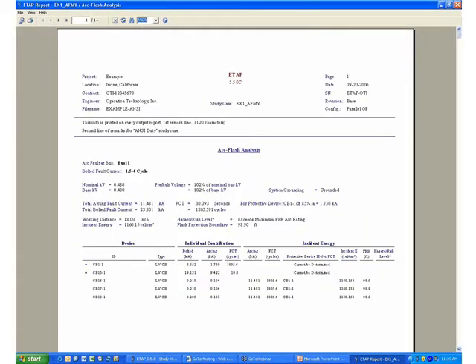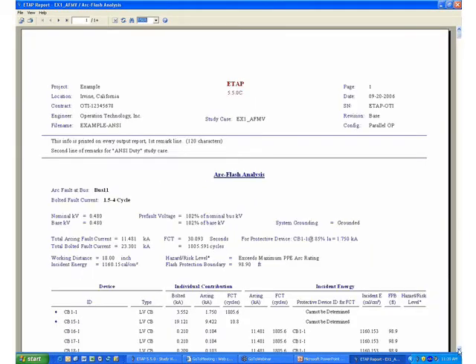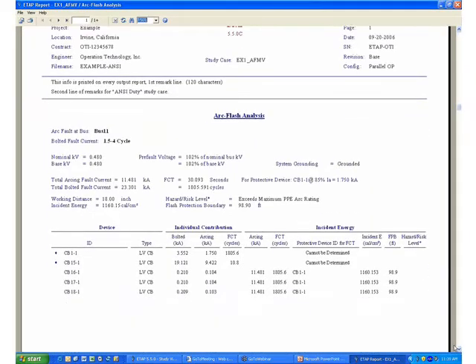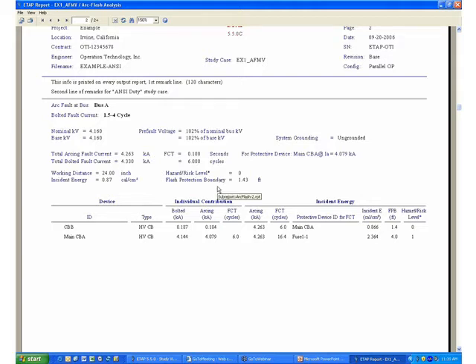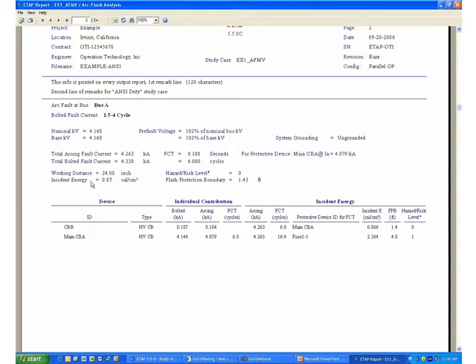The Arc Flash Analysis Report for the bus that we were looking at, which is Bus A, will show you the different results of incident energy that were calculated for this type of equipment. For a fault at the bus itself, the program has determined that the amount of incident energy that could be released is about 0.87 calories, or category 0. Most likely this is because of the fast operating time of the protective device here.